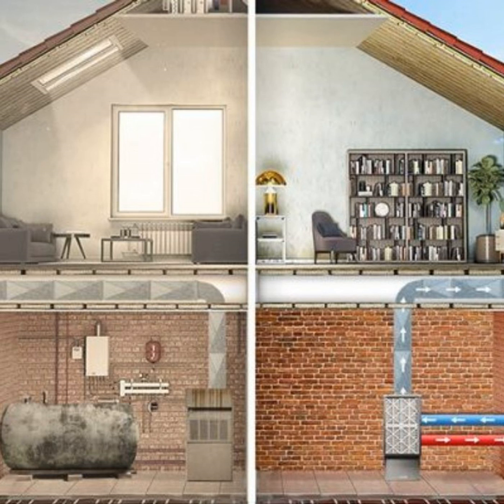So are they like heat exchangers? Yes, heat exchangers are a part of them. In the case of a geothermal heat pump, what we're doing is, as you said, we have a heat exchanger buried in the yard, and that's used to pull heat out of the yard. And then we boost the temperature and distribute it through your home using ductwork. Or if you run the system in reverse, we can take heat out of your home like an air conditioner would, but instead of pushing it into the outdoor air, we're pushing it into the yard through that heat exchanger, which is much more efficient than running an air conditioner.